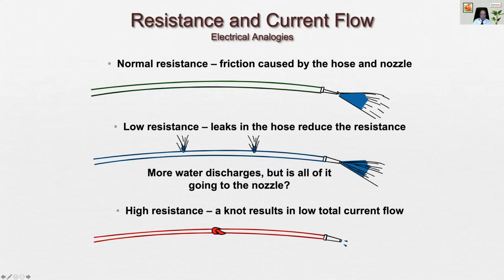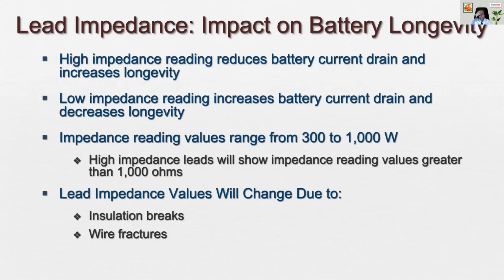Lastly, what happens if you tie a knot in the water pipe? There will be very less water. Similarly, what happens in the pacing lead if there is a fracture, then the current flow decreases significantly, and the impedance, that is the resistance, will go up. So that's how we can give a hydraulic comparison or analogy to the electrical circuit. Now, lead impedance has a very important impact on battery longevity. And if the impedance becomes low for whatever reason, usually because of erosion of the insulation, then the battery drain is very fast. So manufacturers used to give about 300 to 400 ohms impedance in the lead, but now they're building leads with higher impedance. You see, these impedances are built into the leads by the manufacturer.